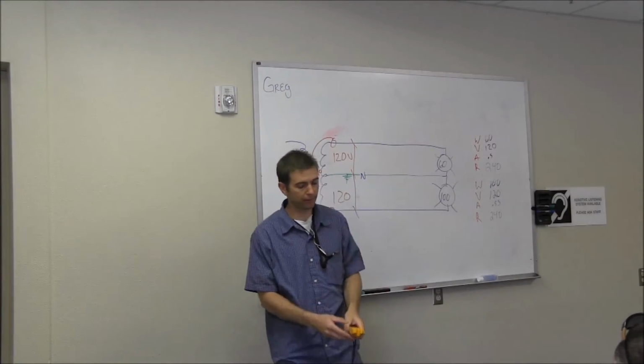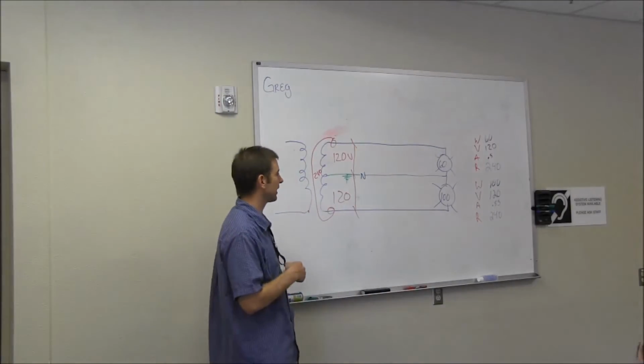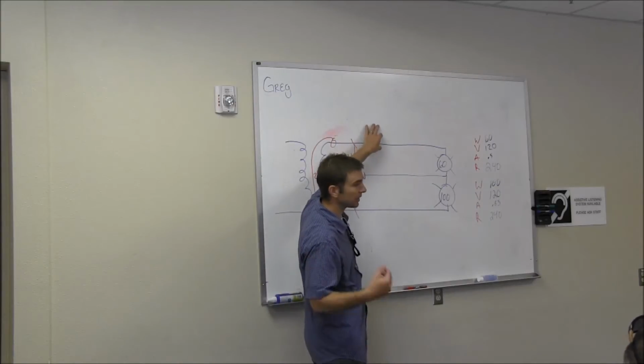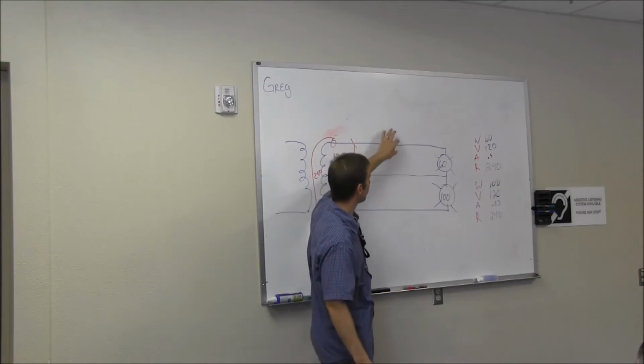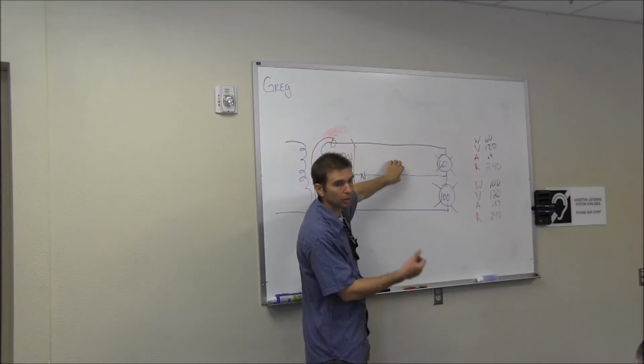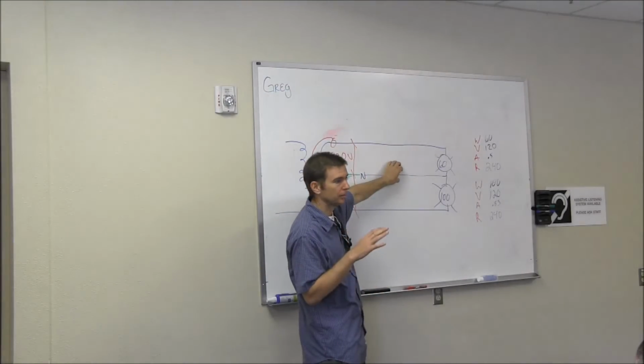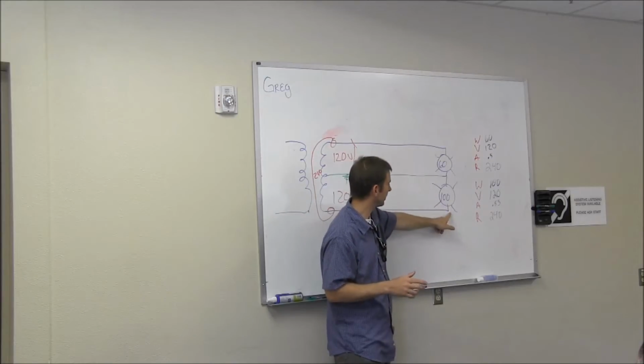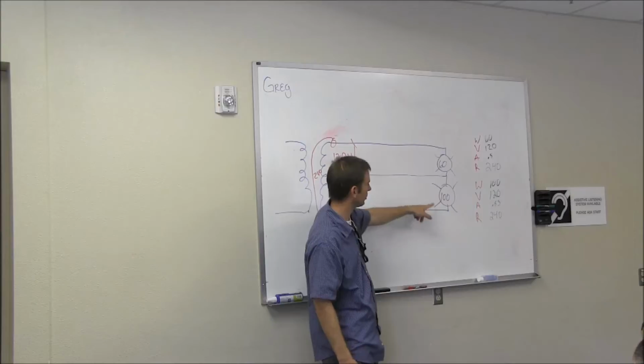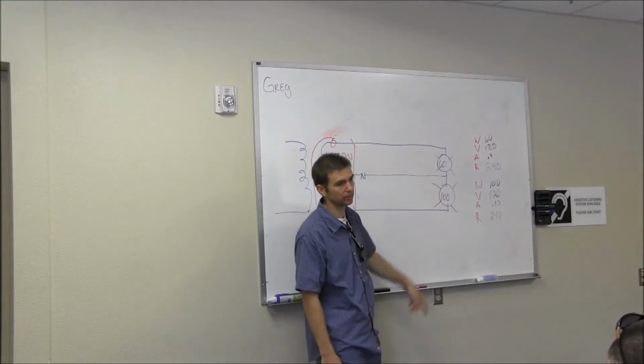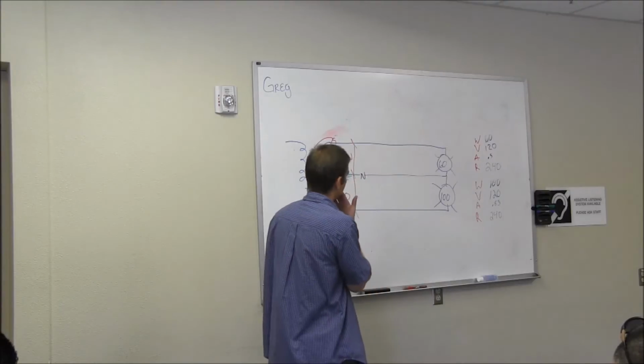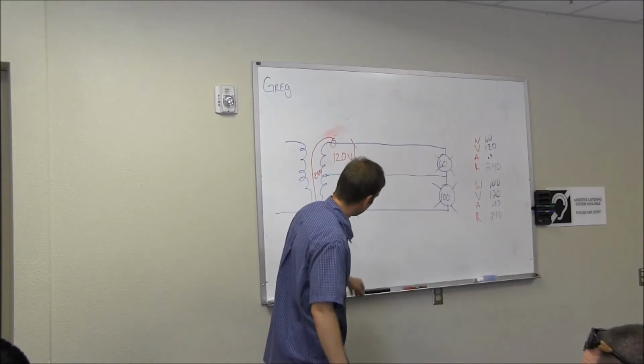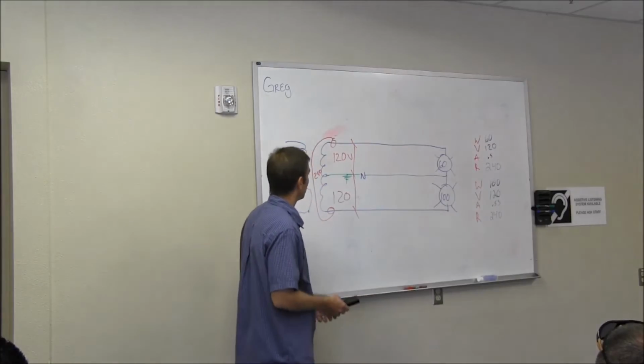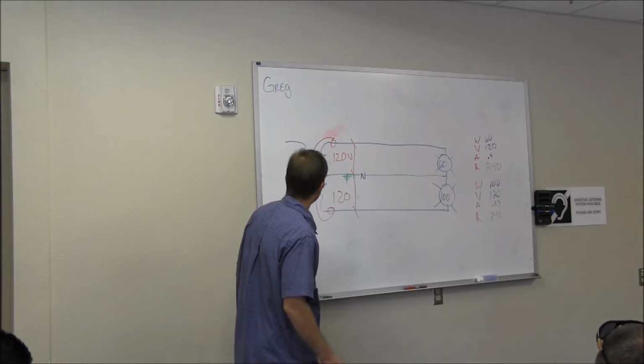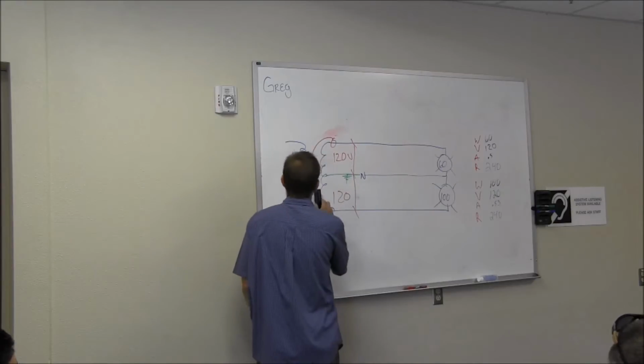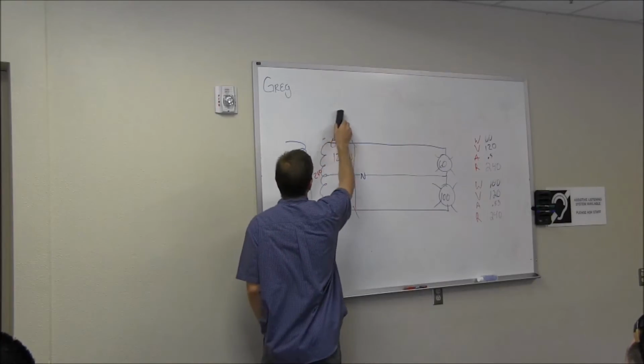So you need to be careful when you're troubleshooting things out in the field. If you're seeing, like we talked about today, 5 amps on this wire, or 0.5 amps on this wire, don't assume I'm going to have 0.5 amps going back on this white wire. Only the unbalanced load is going to be coming back on the neutral. Some of that's essentially coming back on this one. So we have the unbalanced load coming back on our neutral, but we're doing electrical work, we're troubleshooting circuits.